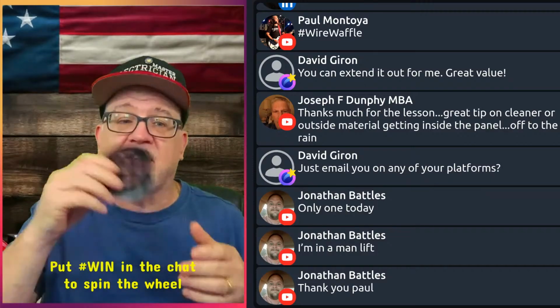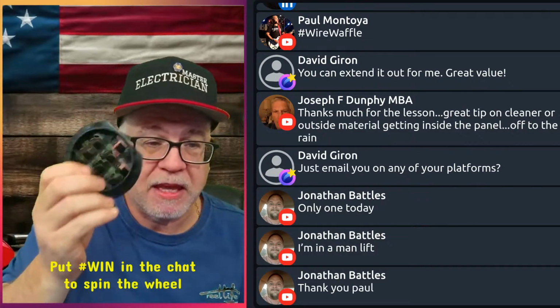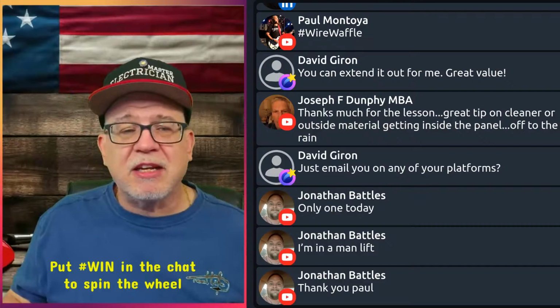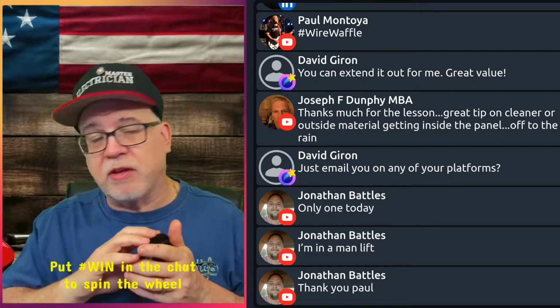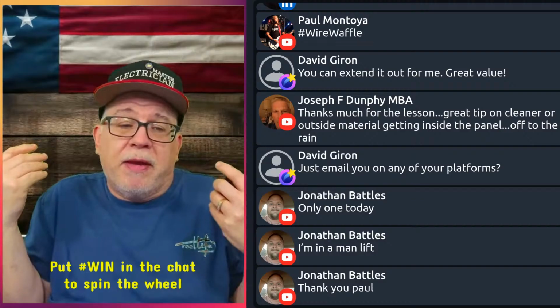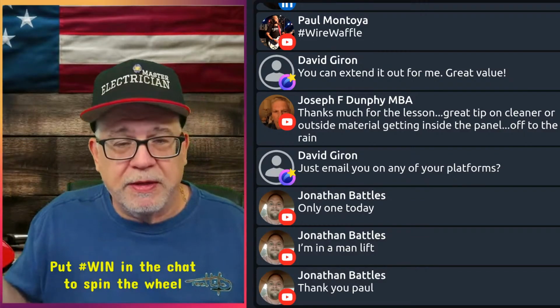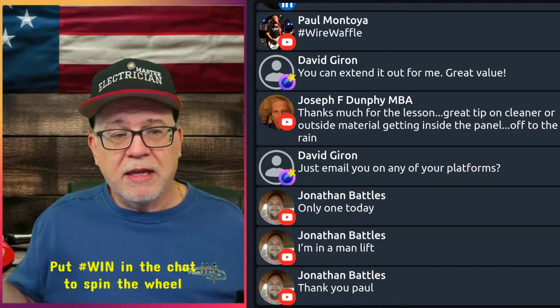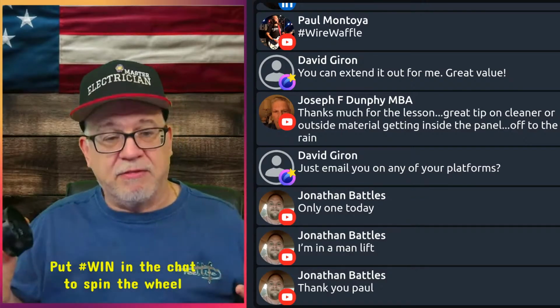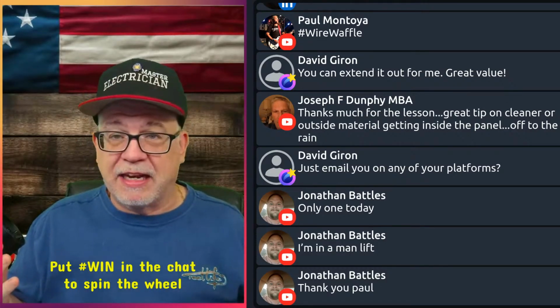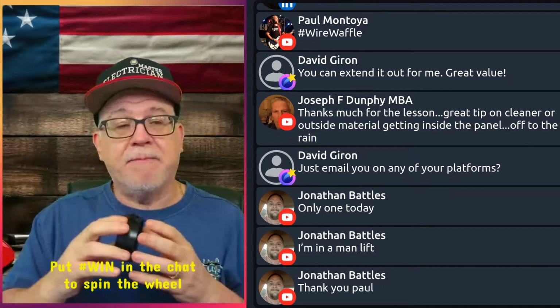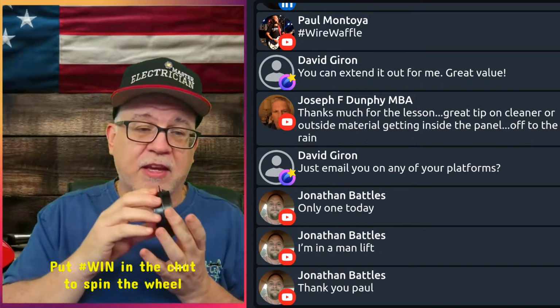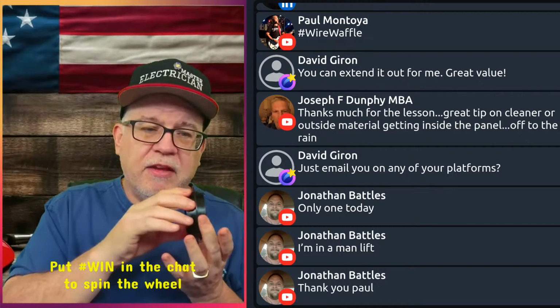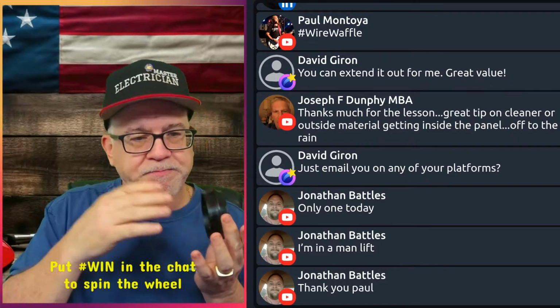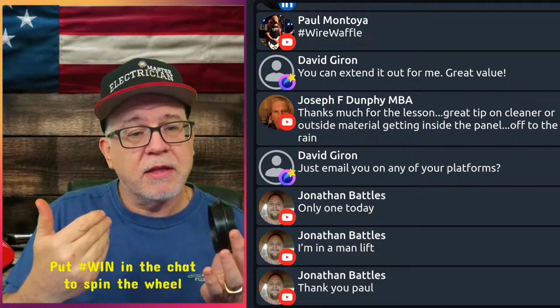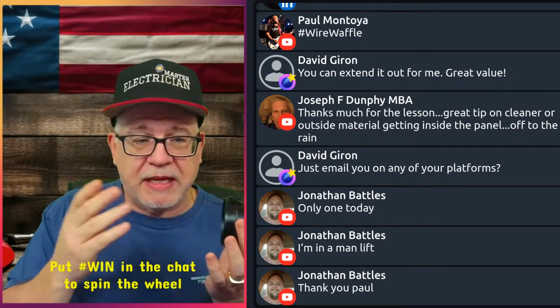And while I'd love to say this solves every issue, there are always going to be little issues. And then of course, those in Arizona will say, well, Paul, we typically mount our panels outside. Well, I can't fix stupid. You're in an area where it's hot as hell and breakers are typically thermoreactive, and you're installing all this outside, then I can't fix stupid. But if you're installing it and this end of the connector is in the wall or goes back into the opening, then I don't have a problem with your transfer. That type of scenario, not going to be an issue at all.